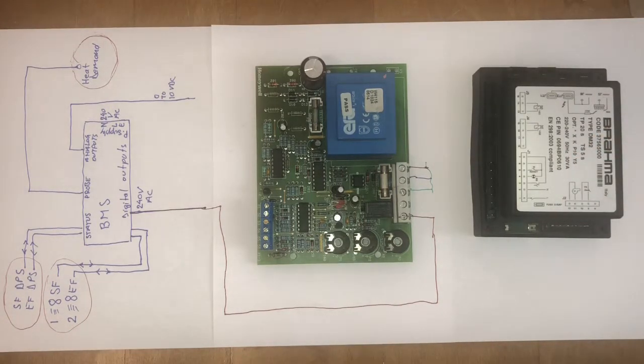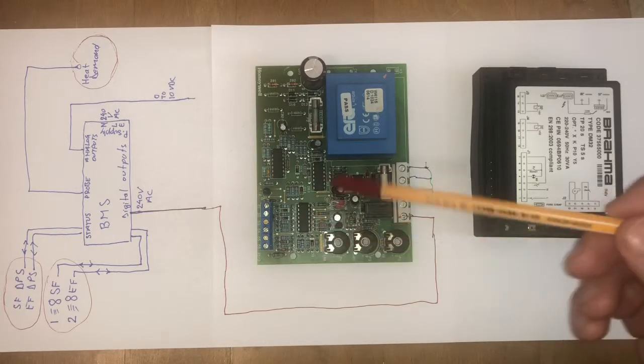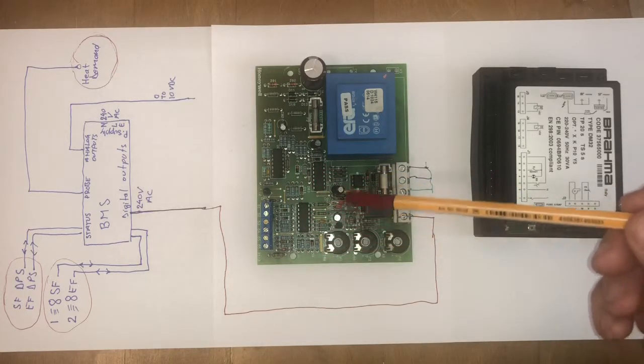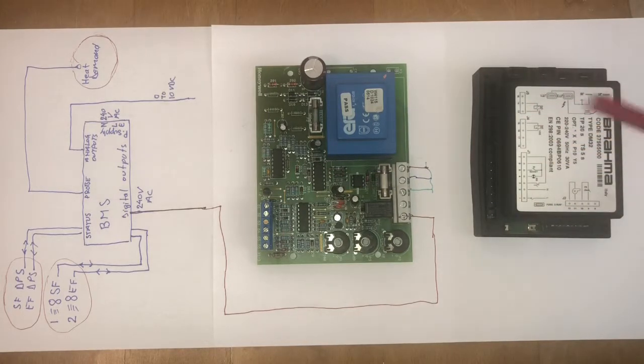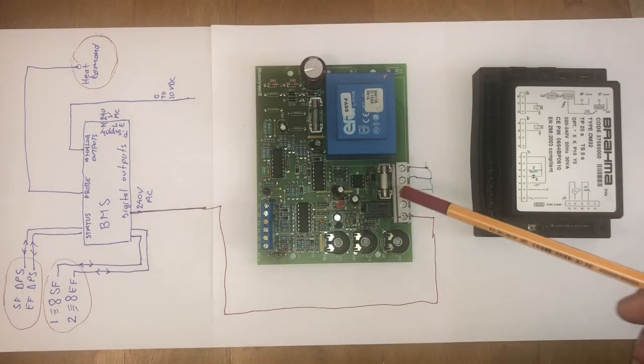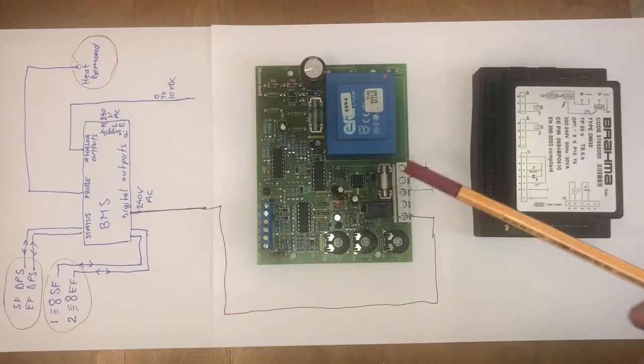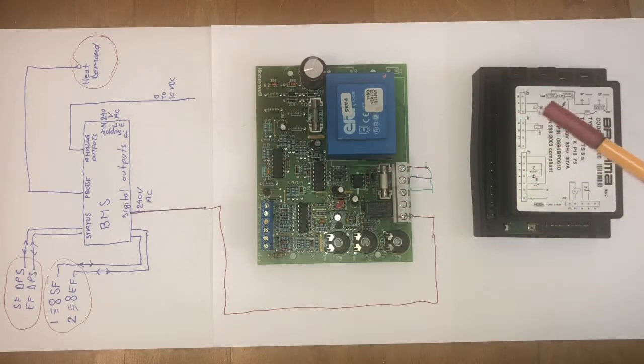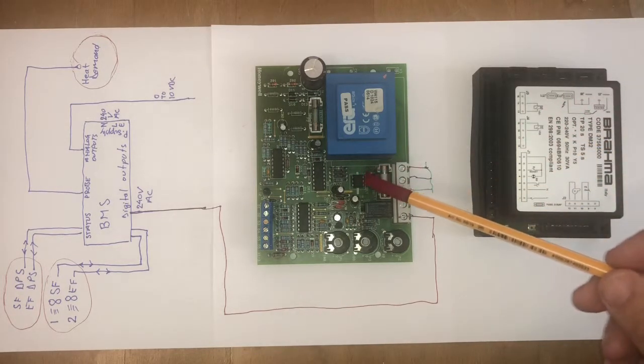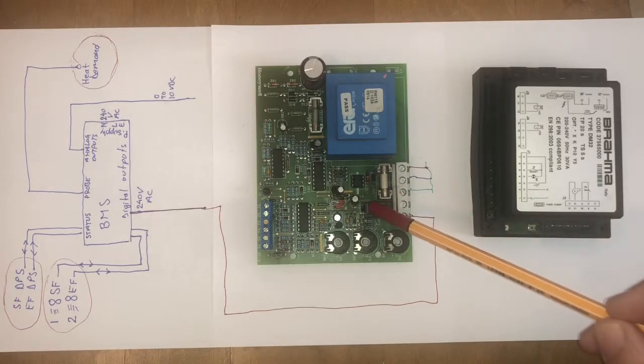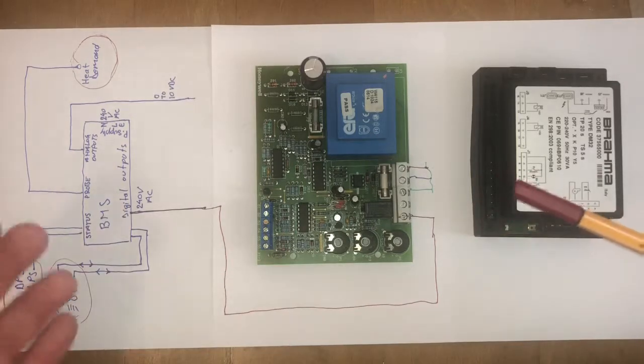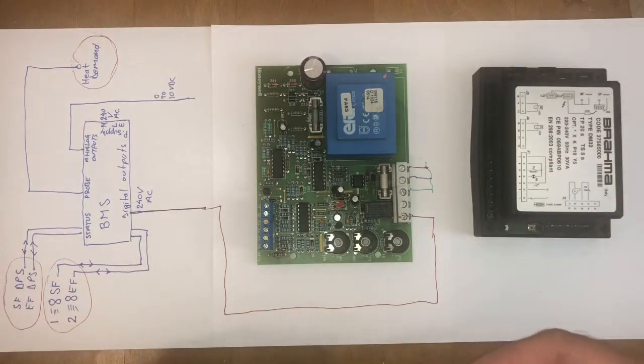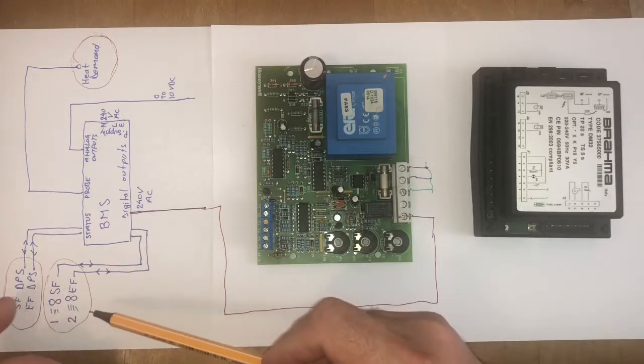I'll get there later on, because I have a video about when I had some problem with some electrical failure inside the PC board control, and the PC board was constantly asking this BMS to run. But even if this one asks the BMS, the Brahma controller to run all the time, it couldn't run all the time, because even if this board was asking and the relay was closed, there was no power here because it was held off by the building management control. I won't go so deep because I will confuse you. All you have to understand is, the fan runs, everything is all right.